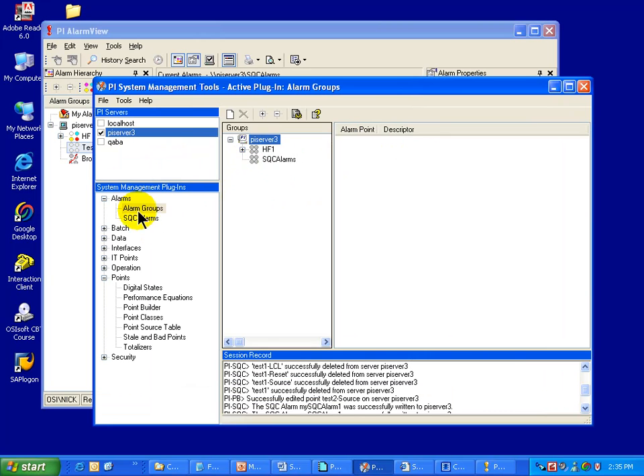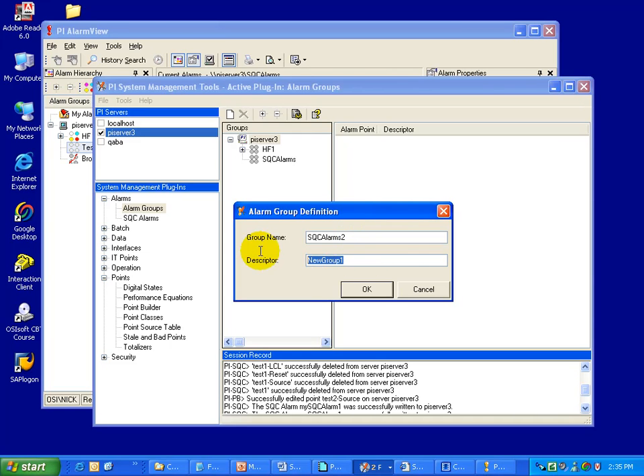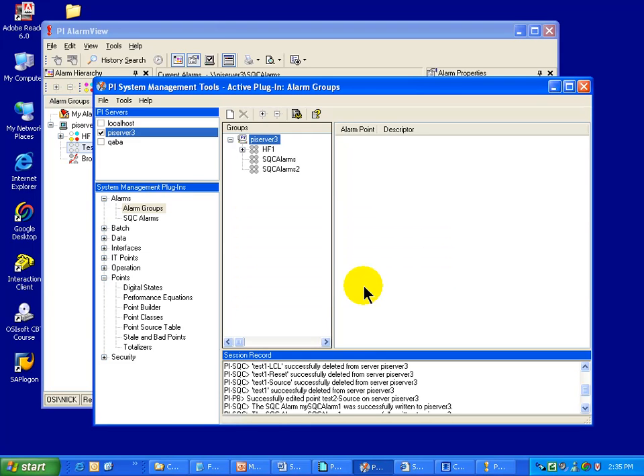This is the Alarm Group Manager. I'll select the PI Server and add a group. You are restricted to having group names with no spaces. Let's call this SQC Alarms 2. The descriptor is actually what you are going to see in the Alarm Viewer. So if I set this up as 'Alarm Group 2' as the descriptor, you'll notice that we are using that in the Alarm View tool — so we now have 2 here.